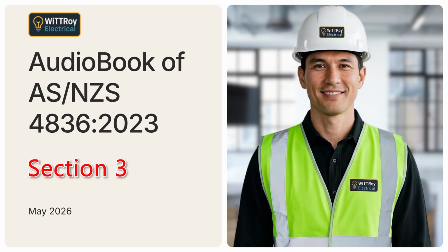The warning message in this clause is very important. All electrical conductors and parts, including neutral and earthing conductors, must be treated as energized until proven de-energized. Always test before touching. This is one of the most important practical rules in the whole standard.